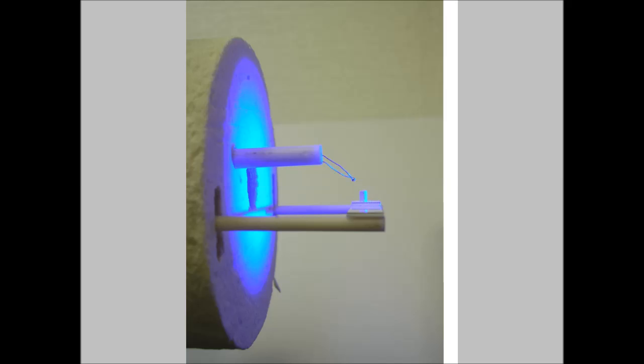A relevant difference between this model and the HSM is that in this instrument the sample is set already in the focus position of the camera. It is not necessary to slide the sample holder into the furnace, but rather the furnace slides over the sample. This prevents the sample from falling into the furnace.